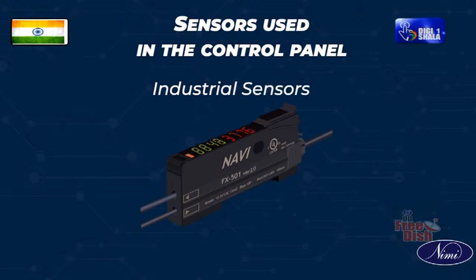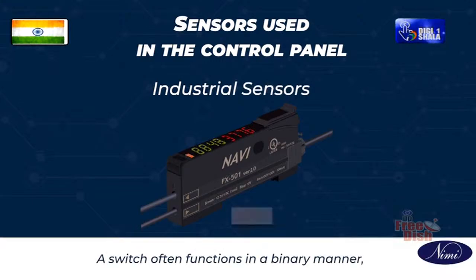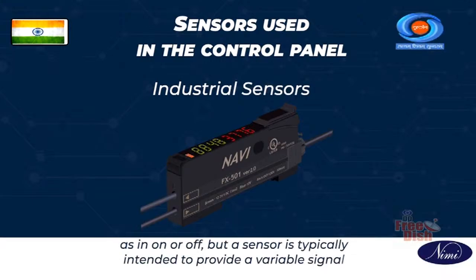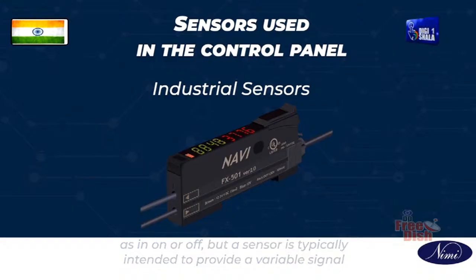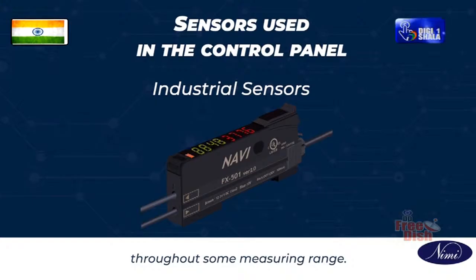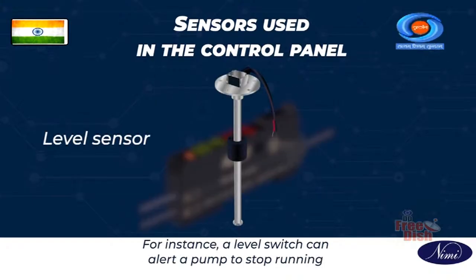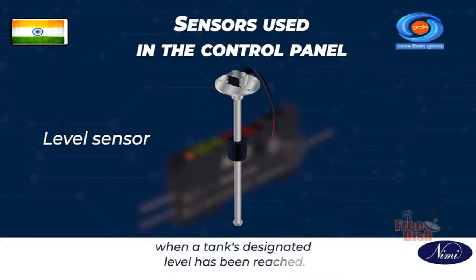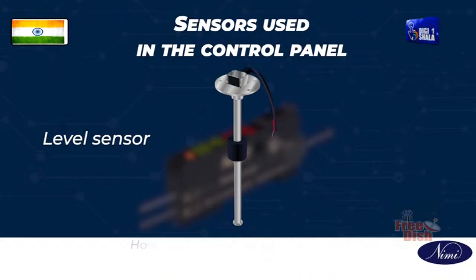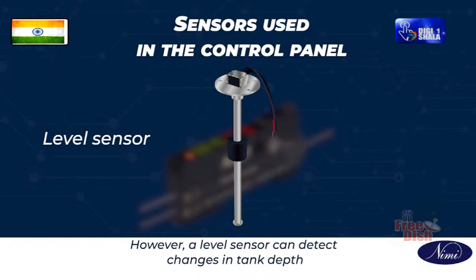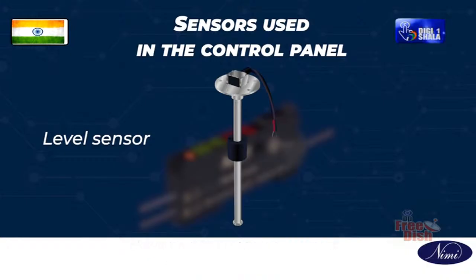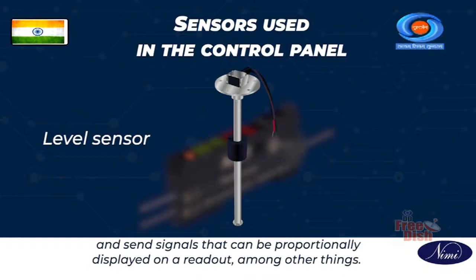Industrial sensors. A switch often functions in a binary manner, as in on or off, but a sensor is typically intended to provide a variable signal throughout some measuring range. For instance, a level switch can alert a pump to stop running when a tank's designated level has been reached. However, a level sensor can detect changes in the tank depth and send signals that can be proportionately displayed on a readout, among other things.